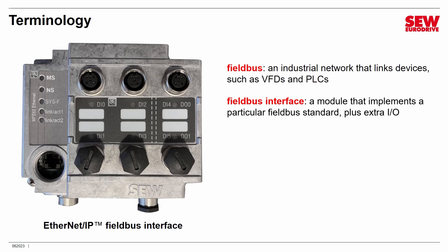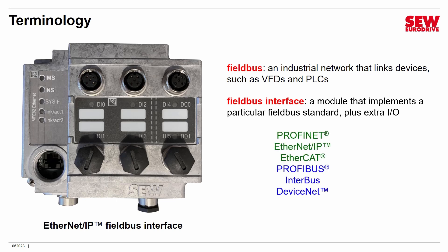Most field bus interfaces also include some extra I.O. connections to expand the capabilities of the MOVIMOT. Currently there are six field bus standards available: PROFINET, Ethernet IP, EtherCAT, PROFIBUS, INTERBUS, and DEVICENET. The ones in green are modern field bus standards based on Ethernet-type networking. The remaining three in blue are classic field bus standards developed in the 1970s or 1980s, based on older networking technologies — legacy field buses, but still common today. SEW EuroDrive supports both the classic and modern Ethernet-based standards.